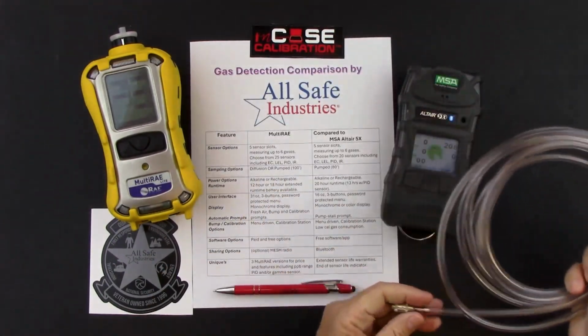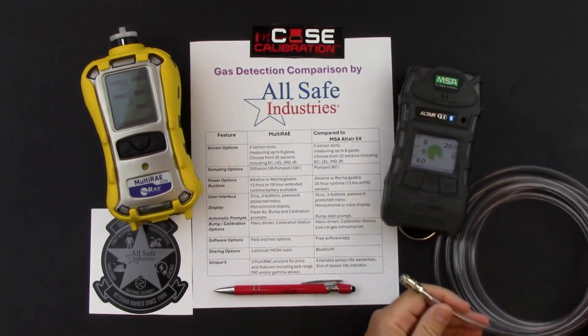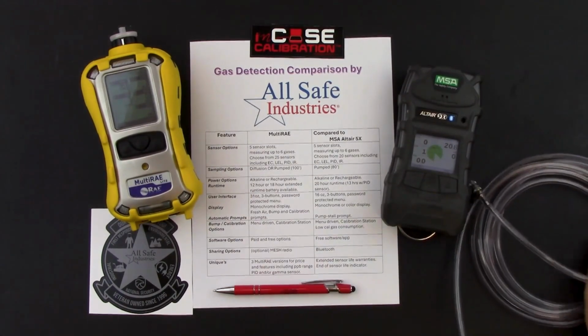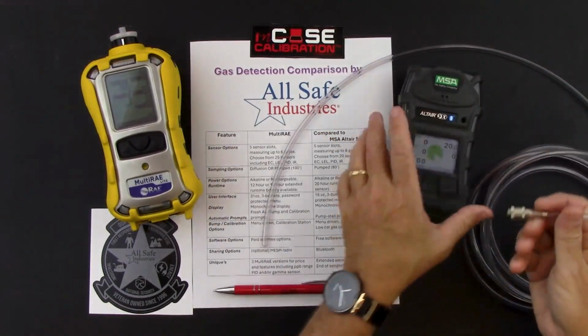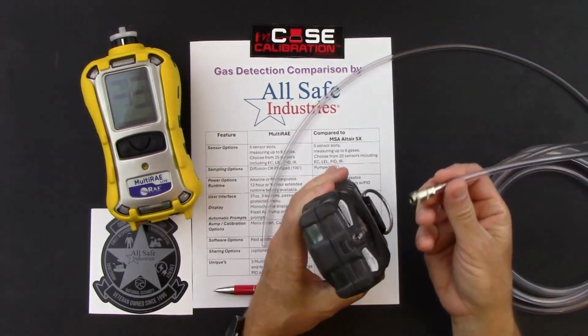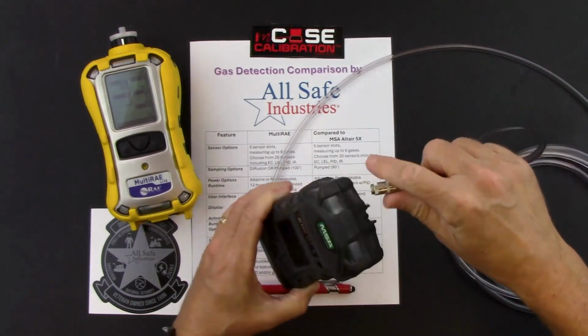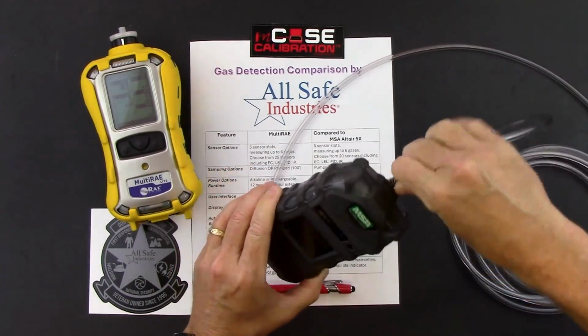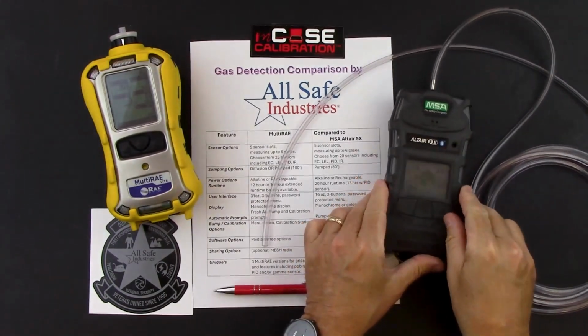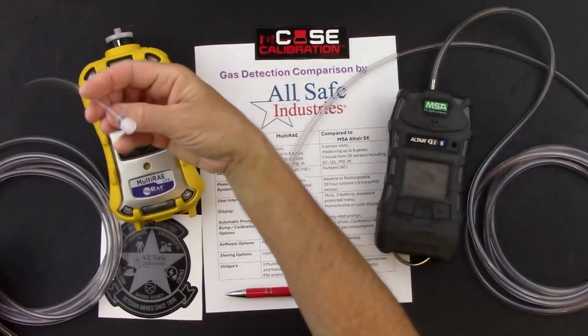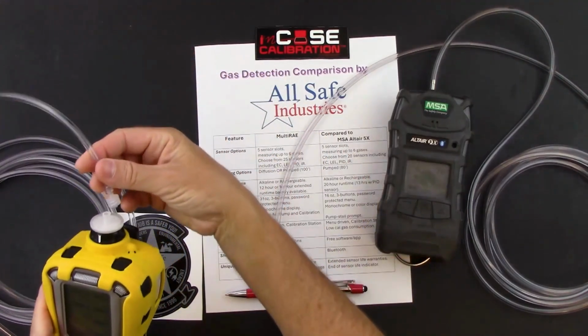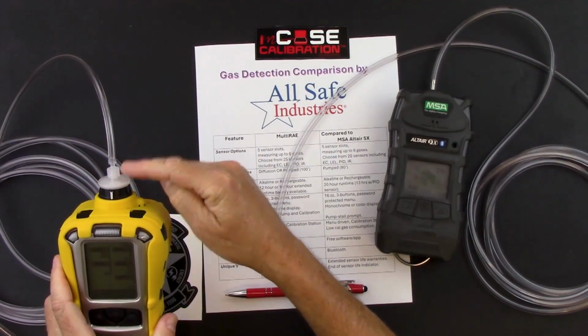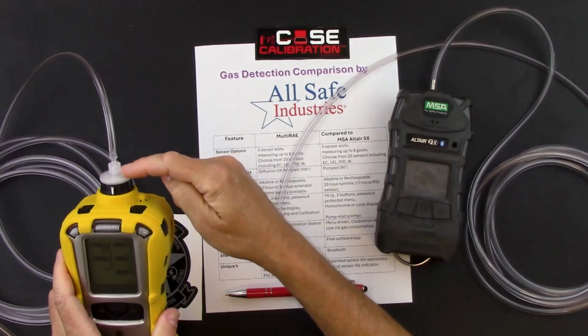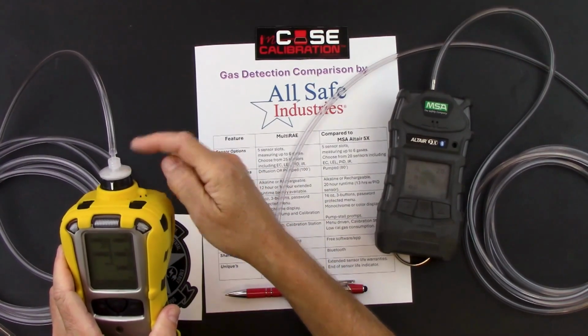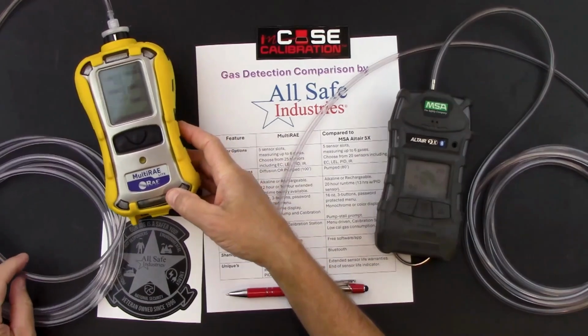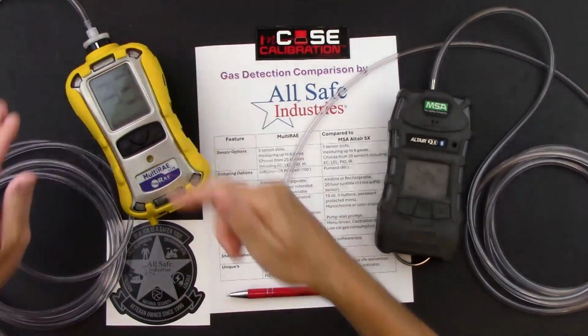feet of tubing. So I have 12 feet of tubing set up for each instrument. With the MSA, it is a quick connect fitting. And so metal fitting for both the pump and for the tubing. You'll just pull the shackle back and then connect it to that metal fitting on the pump inlet. For the MultiRAE, it's a luer fitting. So with luer fittings, you would attach that to the top of the filter. You just want to make sure that the luer fitting is a nice snug fit. You wouldn't want any clean air getting into here and diluting your sample. So make sure you've got a good snug fit when you connect your tubing to your MultiRAE.